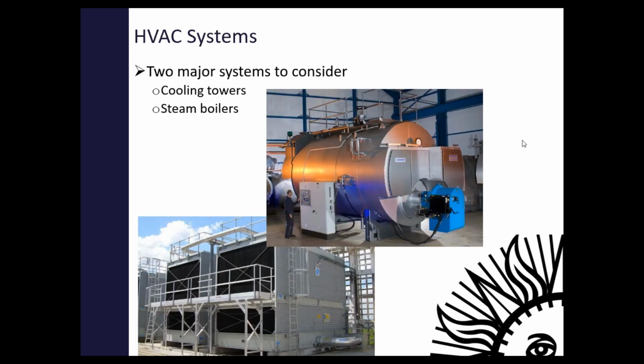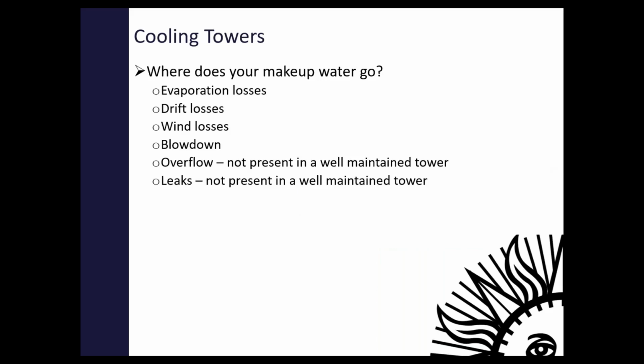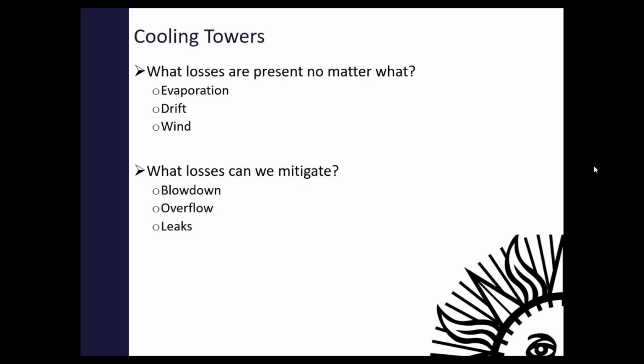HVAC systems, 2 major users of water: cooling towers and boilers, steam boilers. So in your cooling tower, you have six places your water goes. 3 primary are your evaporation losses, drift losses, and blowdown. And the other ones that are minimal or should be minimal are wind losses, overflow, and leaks. Really, overflow and leaks shouldn't be present in a well-maintained tower.